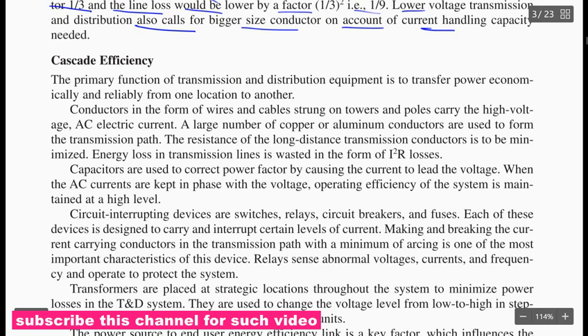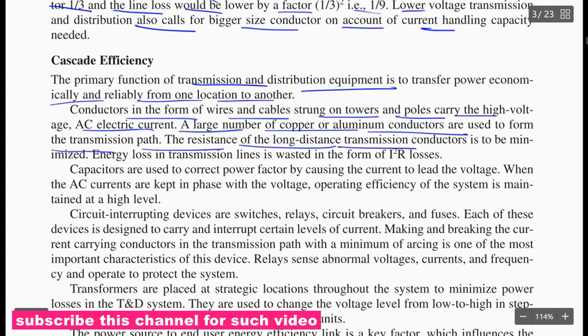Cascaded efficiency. The primary function of transmission and distribution equipment is to transfer power economically and reliably from one location to another. Conductors in the form of wires and cables strung on towers and poles carry the high voltage AC electric current. A large number of copper and aluminum conductors are used to form the transmission path. The resistance of long distance transmission conductors is to be minimized. The energy losses in a transmission line are wasted in the form of I squared R losses.